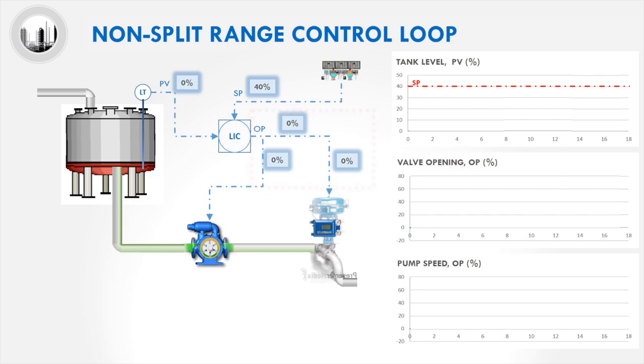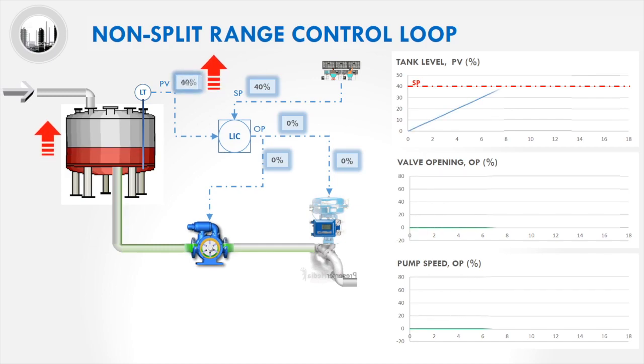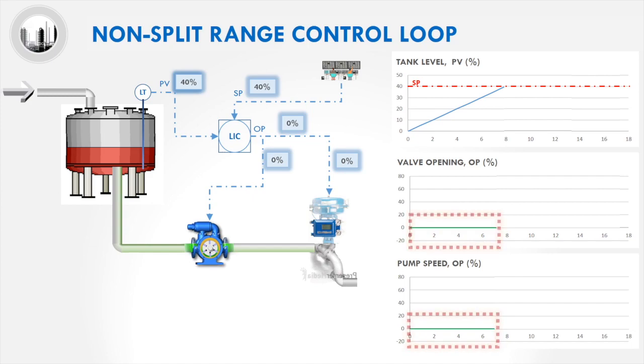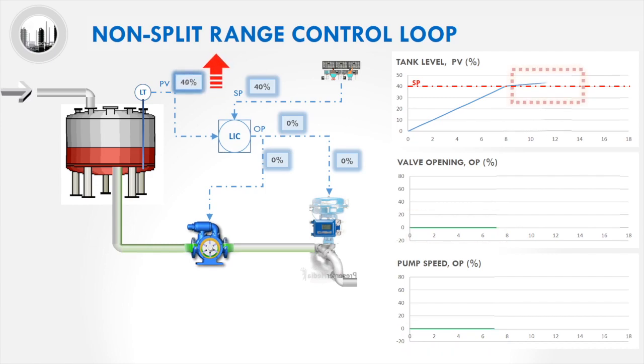Let us evaluate the behavior of the process when we introduce flow into the inlet of the tank. When the level starts to increase, the level transmitter LT will sense the increase of the level. Since the tank level has yet to exceed the controller set point, the output including the valve opening and pump speed are maintained at zero percent. Due to the valve still being fully closed, the tank level will continue to increase.